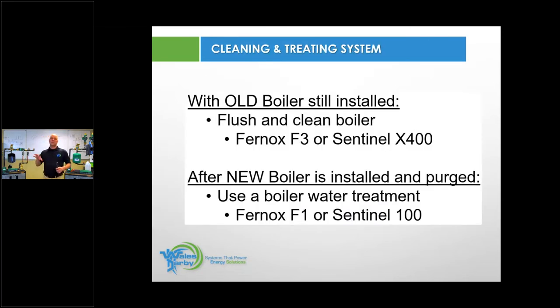The system conditions, this is what I was talking about earlier. Again, these are cleaners. These would go into the boiler system prior to removing the boiler. You put these in, they circulate around the system, warm water, they activate quicker. If you had a catastrophic boiler failure, this would be done through a bucket and pumped into the system. But if your boiler is still in, you can shoot this right into the boiler, let it circulate within the system. It'll go through, and think of a nylon brush going through the inside of your pipes, cleaning up all those pipes, bringing that debris back. So when you remove that boiler, you're going to take all that dirt and debris out. Then you'll flush the system and you'll have a nice clean system to hook that new boiler up to.